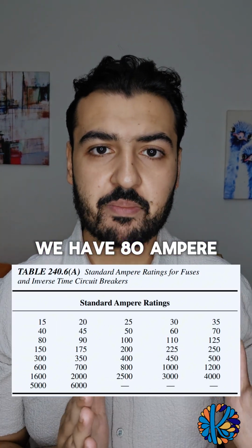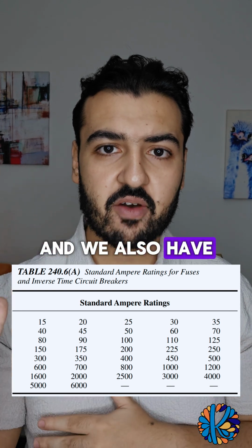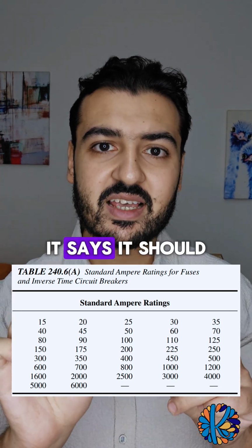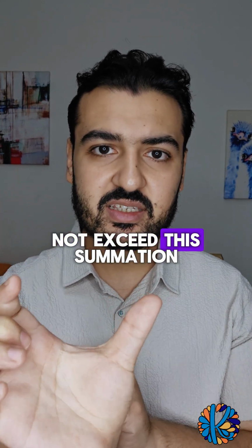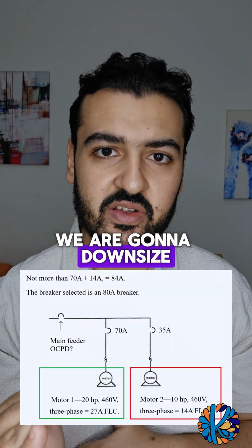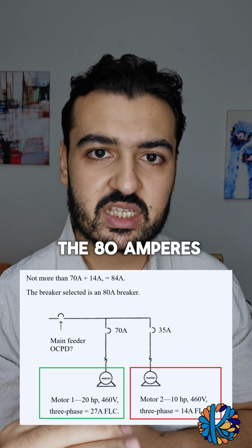We have an 80 ampere circuit breaker and we also have a 90 ampere circuit breaker. It should not exceed this summation, so we are going to downsize the breaker and select the 80 amperes.